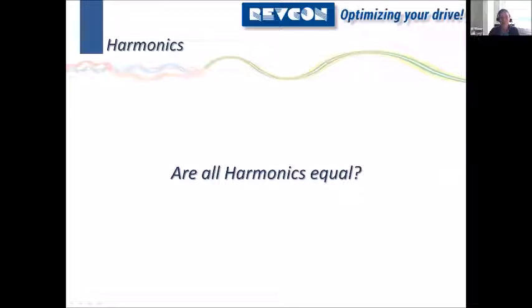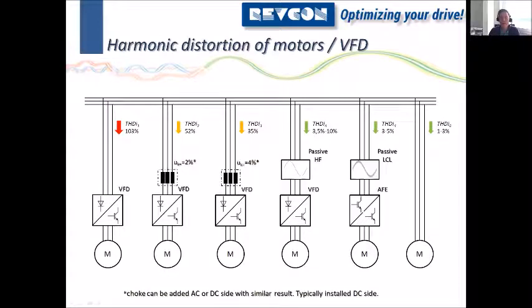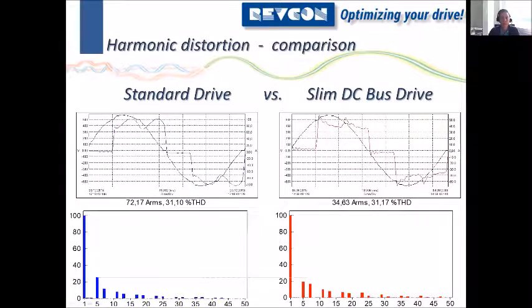As I mentioned before, I already answered this question, to be honest. Are all harmonics equal? They are definitely not. To understand this, we should have a look at this picture again. If we look at the second picture, and if we measure a THDI on a drive of 35%, we could assume that this is a high quality drive. We could assume this must have a 4% choke inside. But I'm afraid it's not that simple, because there is a quite new phenomenon, so-called slim DC bus drives or eco drives. These are not bad guys, but you should be careful when using them because they have a completely different spectrum than a standard drive.